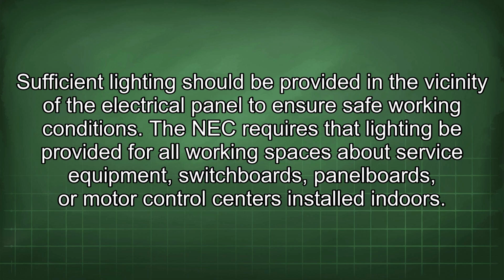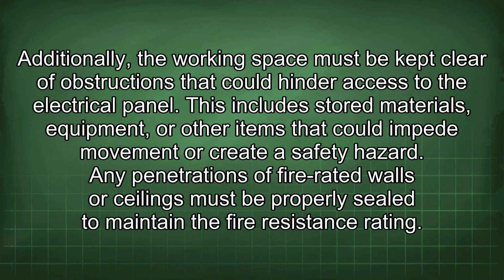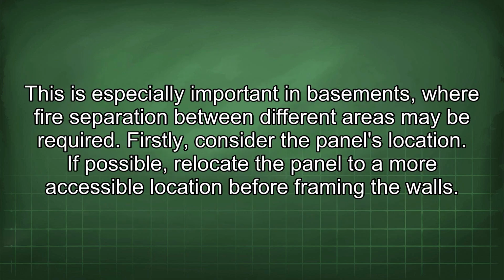The NEC requires that lighting be provided for all working spaces about service equipment, switchboards, panel boards, or motor control centers installed indoors. Additionally, the working space must be kept clear of obstructions that could hinder access to the electrical panel. This includes stored materials, equipment, or other items that could impede movement or create a safety hazard. Any penetrations of fire-rated walls or ceilings must be properly sealed to maintain the fire resistance rating. This is especially important in basements, where fire separation between different areas may be required. Firstly, consider the panel's location. If possible, relocate the panel to a more accessible location before framing the walls.